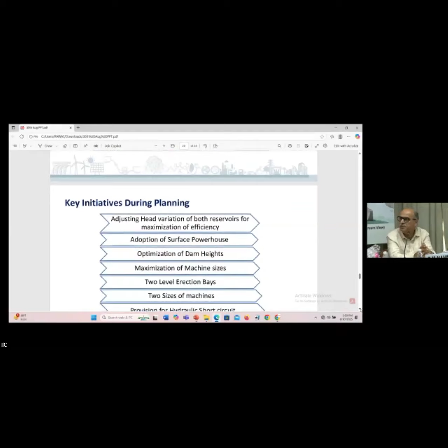So when we came down to the idea of fixed speed machines and two-speed machines, we reconfigured the project entirely. We adjusted the head variation in both reservoirs to get the maximum output of the machines, because in fixed speed machines, the efficiency curve drops badly once you go to a larger head variation. So the reservoir head variation was adjusted accordingly.